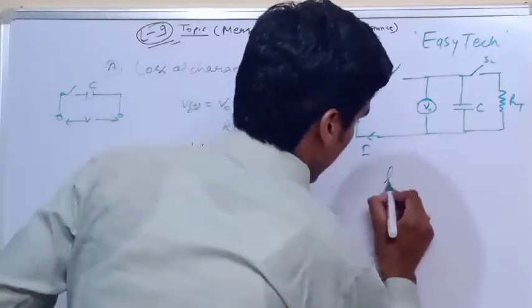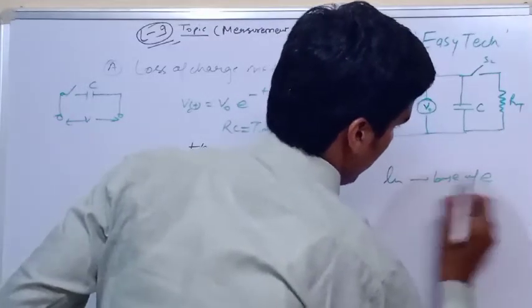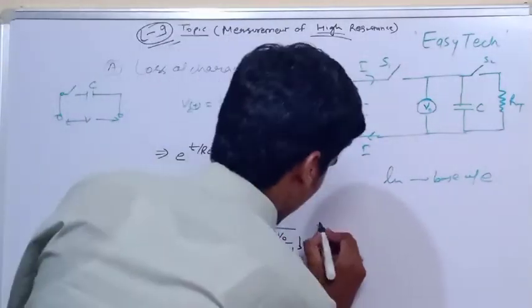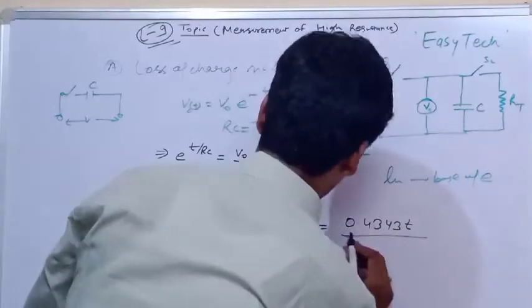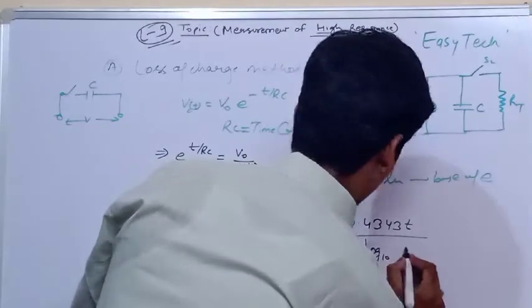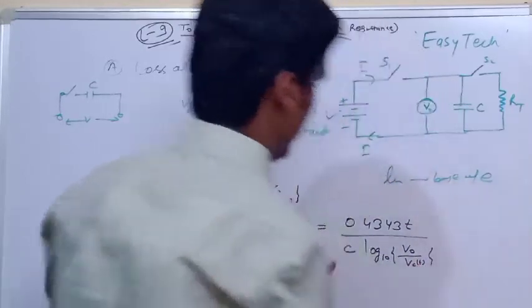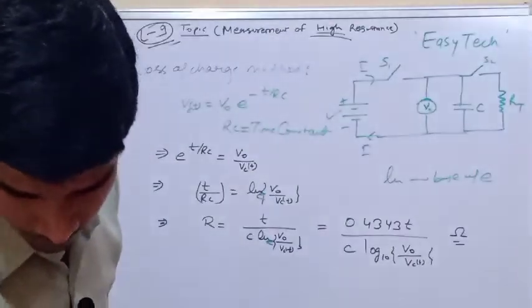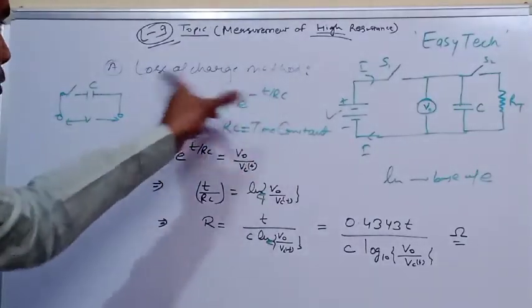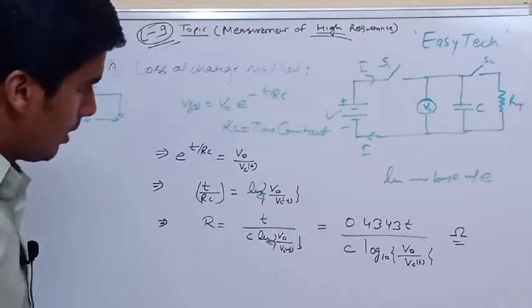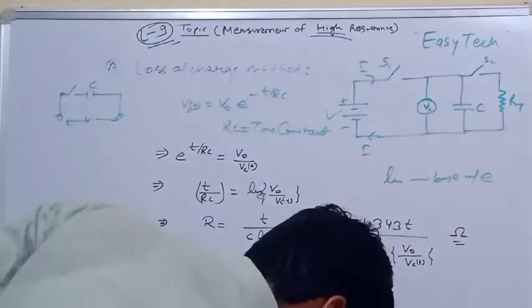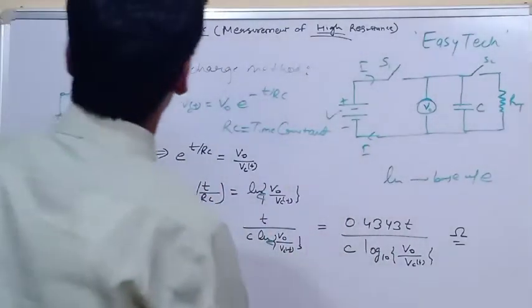From the derivation, R is equivalent to: R = t / (C · ln(V₀/Vct)), where ln has base e. If you want to convert to base 10 logarithm, the formula becomes: R = 0.4343 · t / (C · log₁₀(V₀/Vct)), with the result in ohms. This is the loss of charge method formula used to find the unknown high resistance.